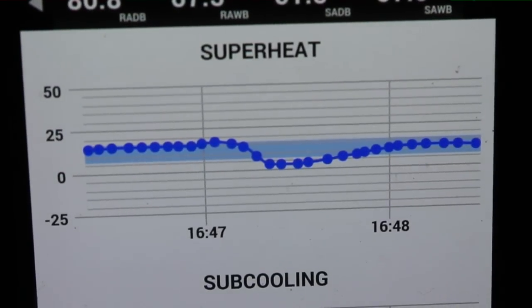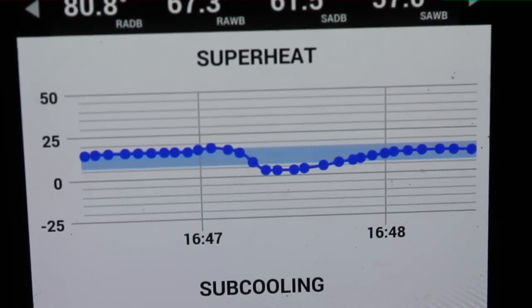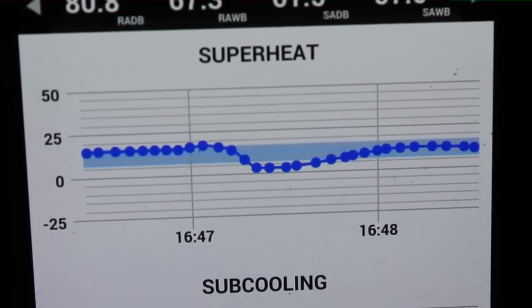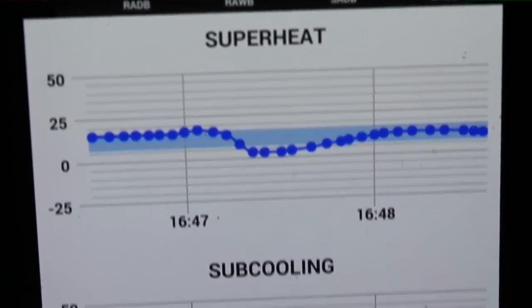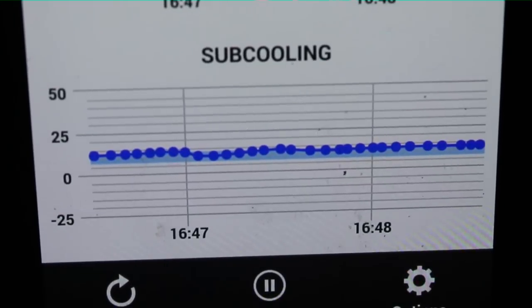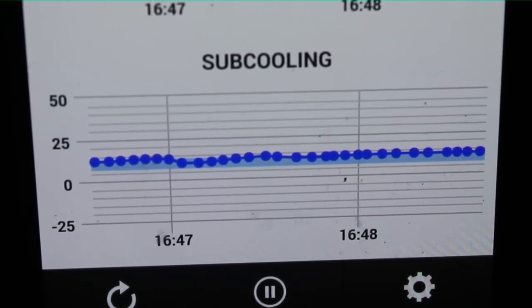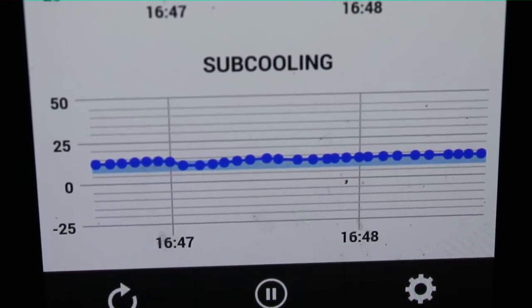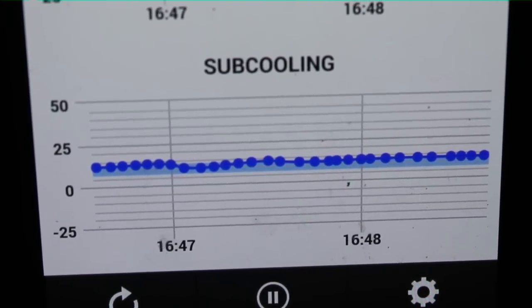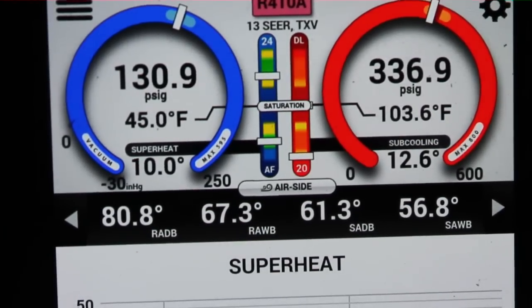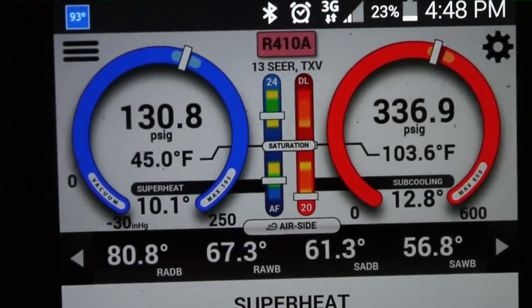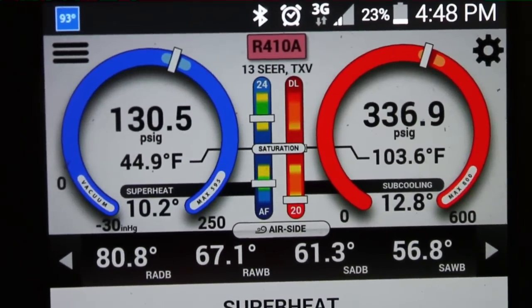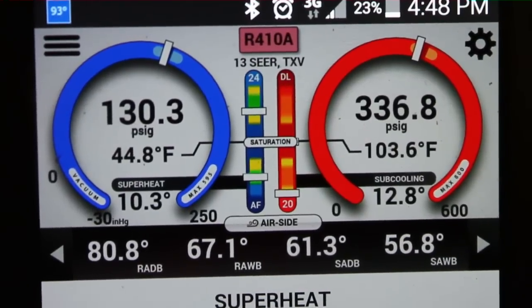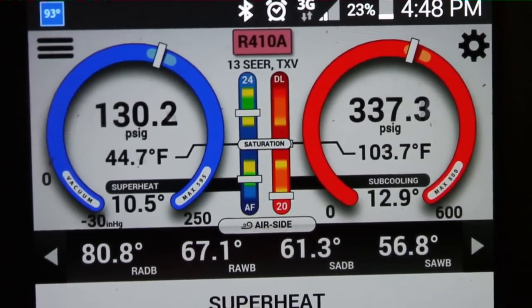You can see here, that's where I took the door off to adjust the TXV. You can see the sharp dip in superheat as air bypassed the coil. And there's also a dip on the subcooling chart, but it stayed relatively on target the whole time. So hopefully we're about done here. As we see, our superheat has bottomed out a little bit lower. Our subcooling is definitely lower. So we're about squared away. Hopefully happy for today. May make a few more adjustments, but I think we're pretty much done. And I'll see you guys on the next one.